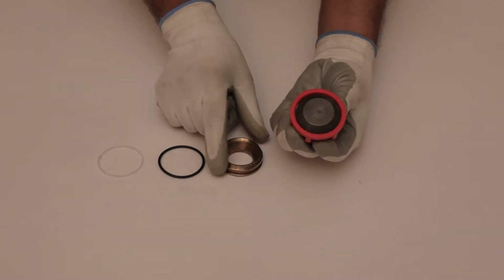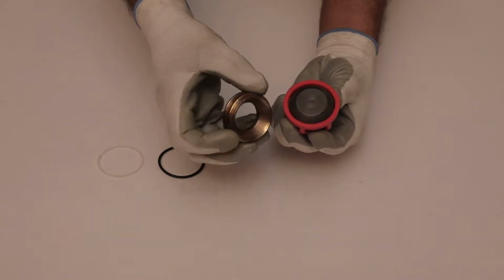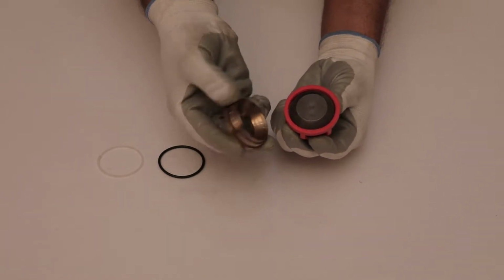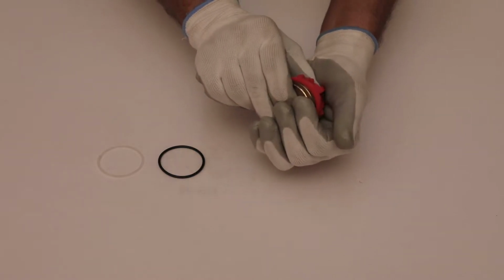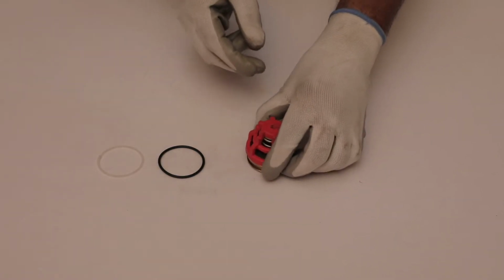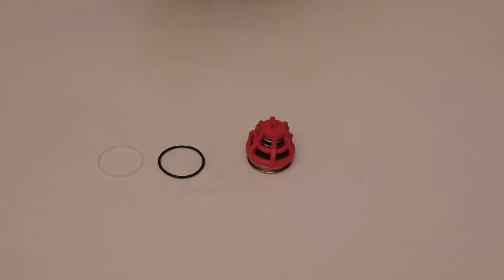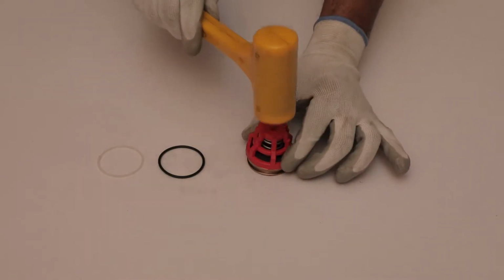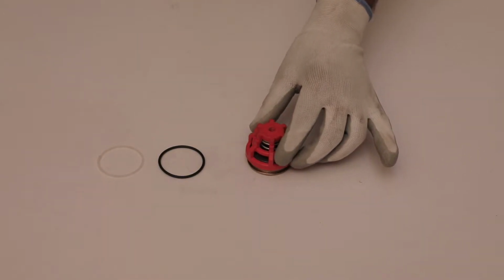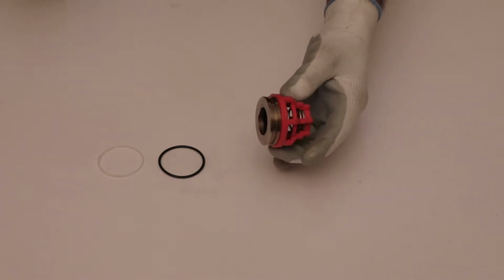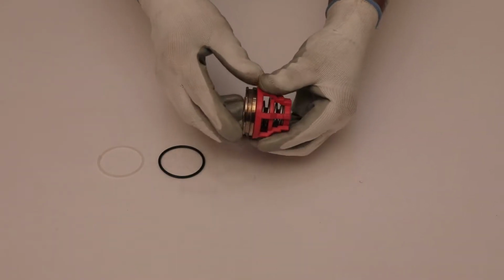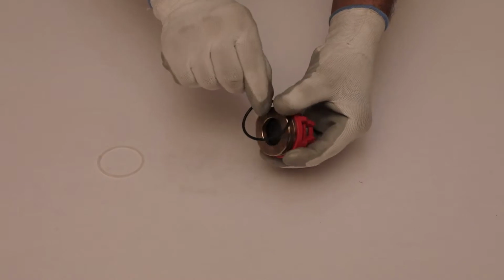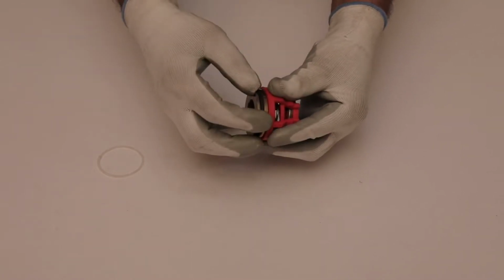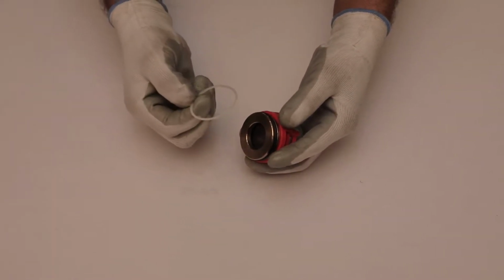Assemble suction and discharge valve seat with valve guide in such a way that its flat surface will face outward. Gently push valve seat by rubber hammer to fix it with suction and discharge valve guide. After that, assemble the O-ring and back ring for valve seat inside groove of the suction and discharge valve seat.